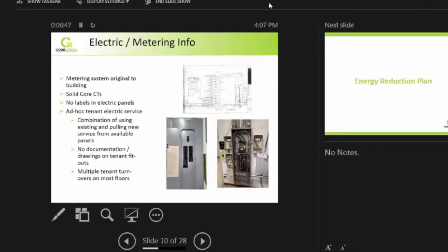In terms of the metering system at the building, the metering system and infrastructure were original to the building. It utilized power line communication, so there was no communication wiring anywhere throughout the building. The big difficulty from our standpoint when trying to retrofit these systems is not necessarily the existing communication or hardware—it's this third bullet here: no labels in the electric panels.